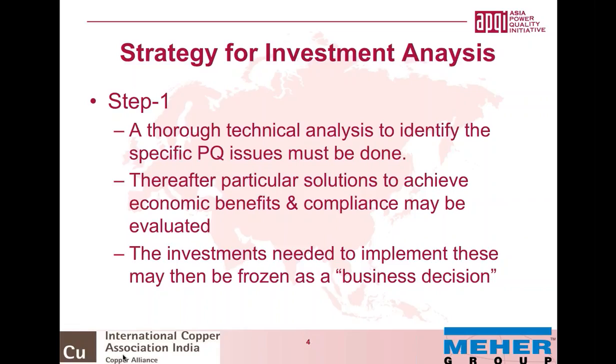It is thereafter necessary that particular solutions to achieve economic benefits and compliance be evaluated. Let's say we want to improve power factor, reduce harmonic distortion, or we have a sensitive load where voltage fluctuation from the grid is not acceptable, and therefore we don't want a galvanic connection - meaning it should not come through a transformer supply, but be isolated from such galvanic connection. So we will put a double conversion UPS to ensure there is no connection between the supply and load side in terms of waveform and amplitude of the voltage. These are different solutions that can be contemplated.